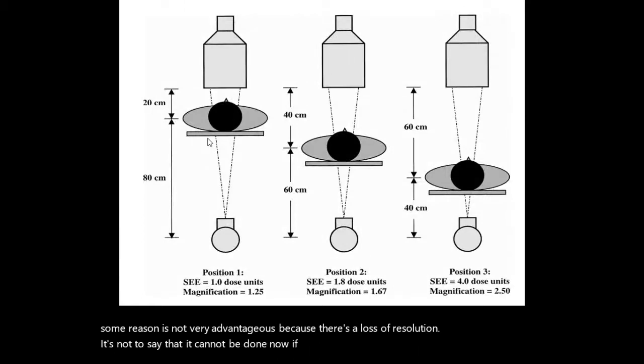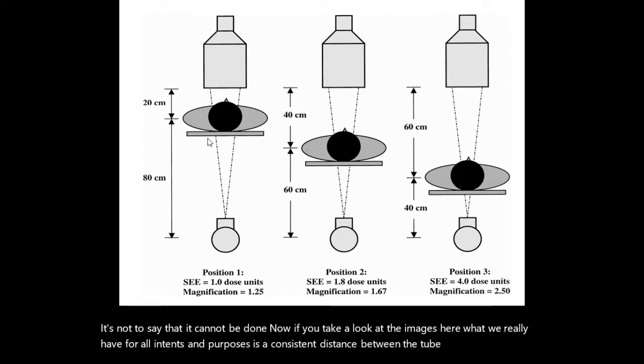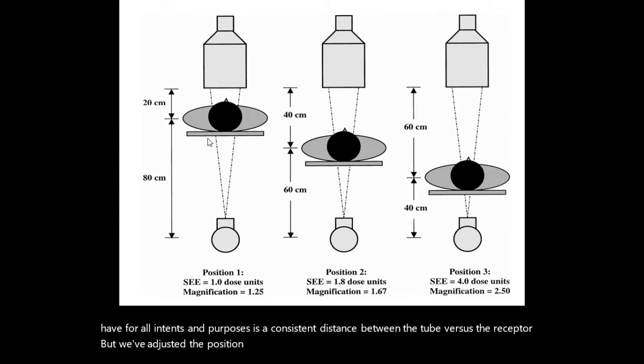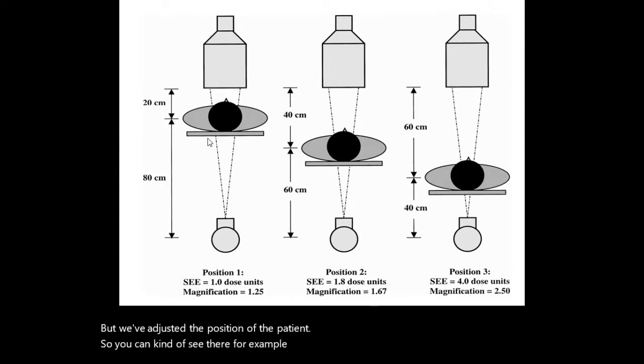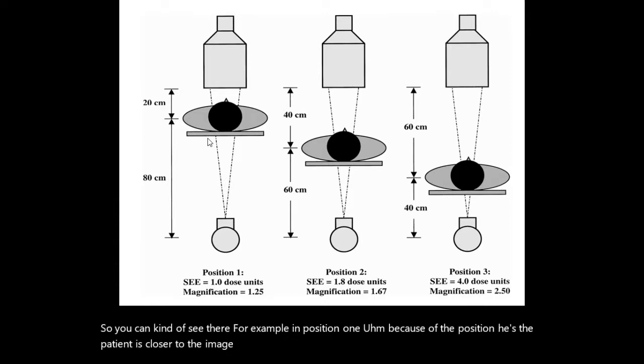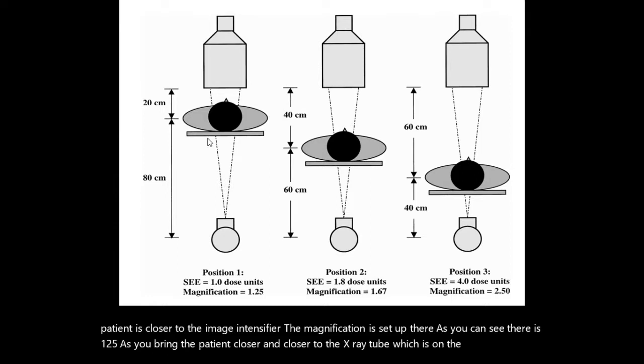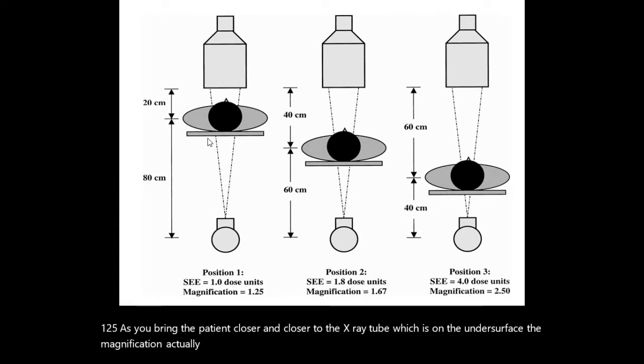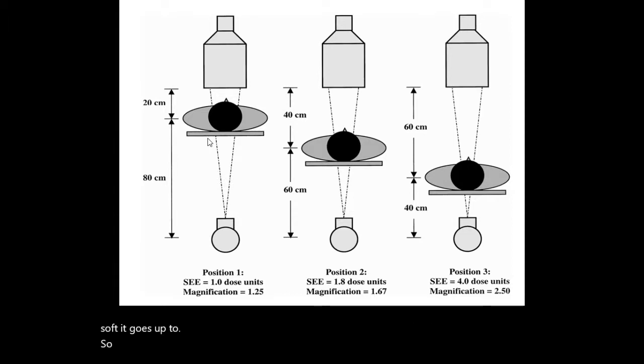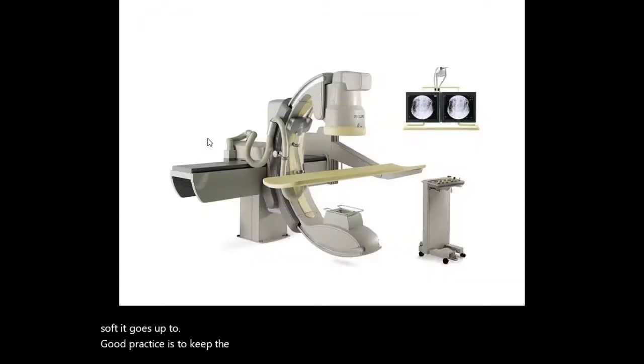Now, if you take a look at the images here, what we really have for all intents and purposes is a consistent distance between the tube and the receptor, but we've adjusted the position of the patient. In position 1, the patient is closer to the image intensifier, and the magnification, as you can see, is 1.25. As you bring the patient closer and closer to the X-ray tube, which is on the undersurface, the magnification increases. You might also notice that the dose goes up too. So good practice is to keep the patient as close to the receptor as we can.